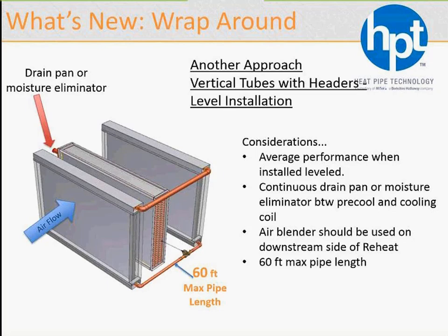The distance between pre-cool and reheat has been extended to about 60 feet. For wraparound heat pipes, almost never will it be used, but should the need arise for a 60-foot span between pre-cool and reheat. The height per section is limited to 30 inches for this particular product. So larger systems may require multiple sections stacked. Could be 2, could be 3 sections, and each stack would have either 1 circuit or 2 circuits depending on the number of rows. A 2-row system will have basically 1 vapor and 1 liquid line per section, and the stack will be about 30 inches high.